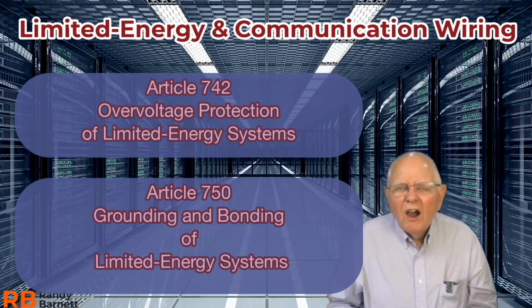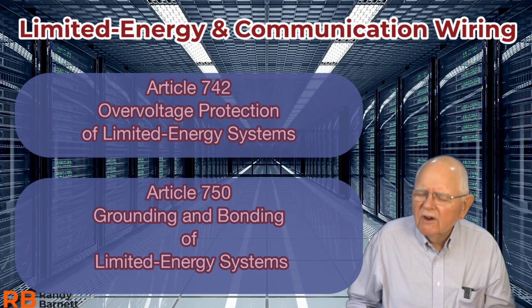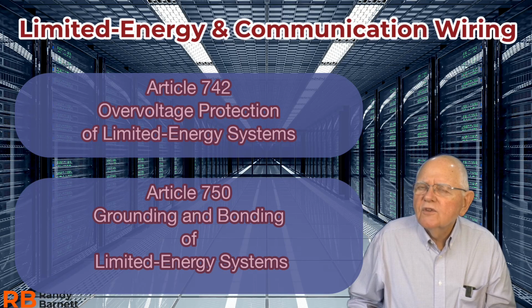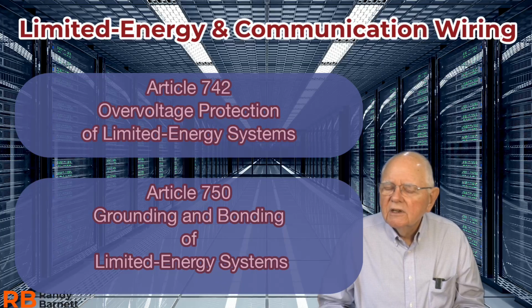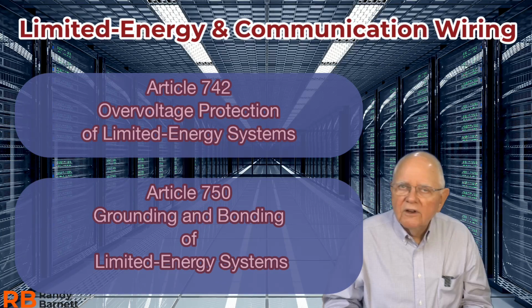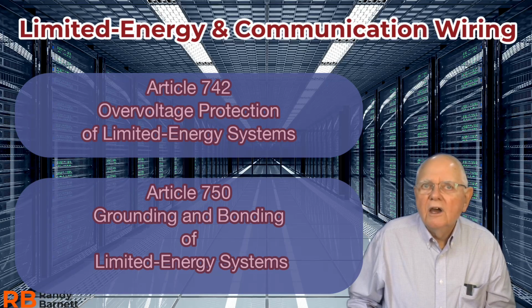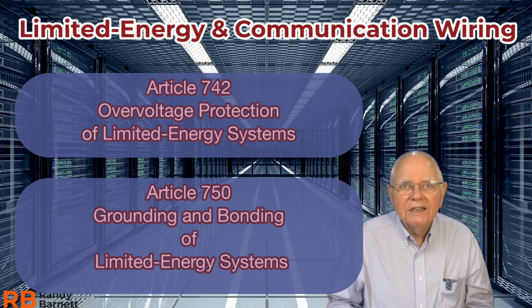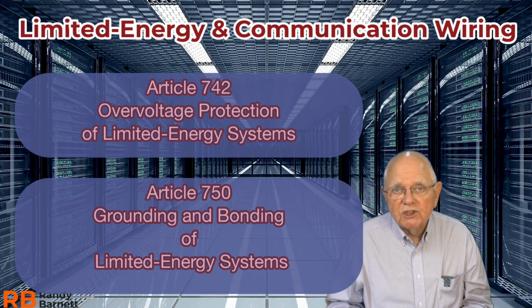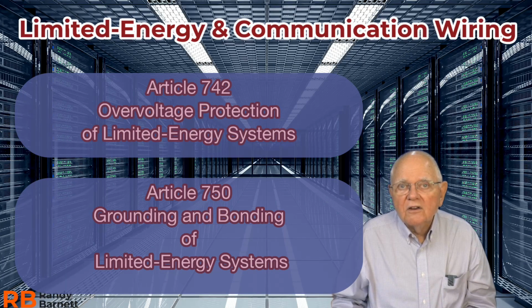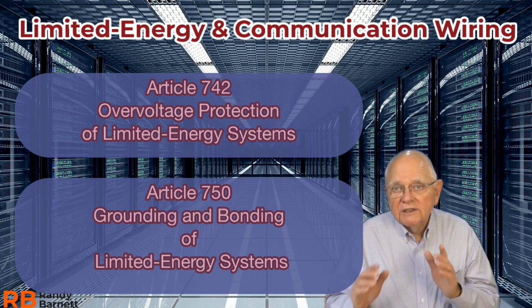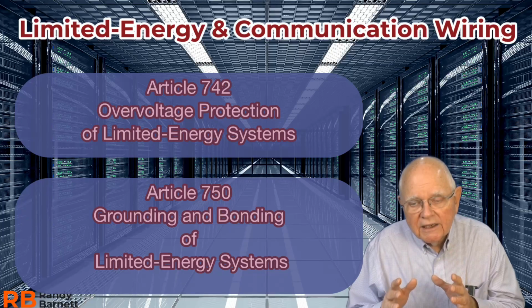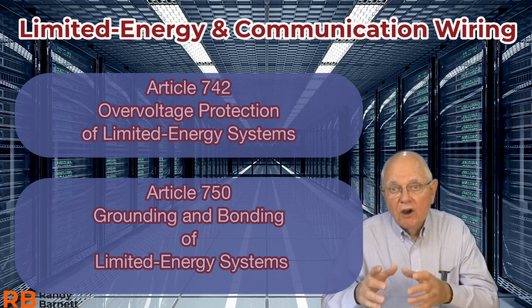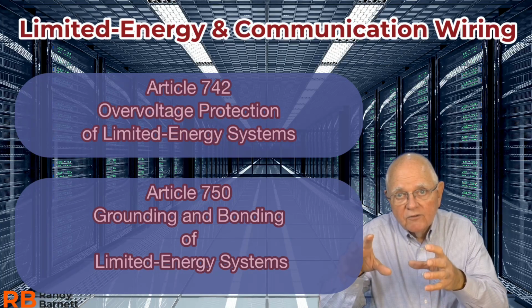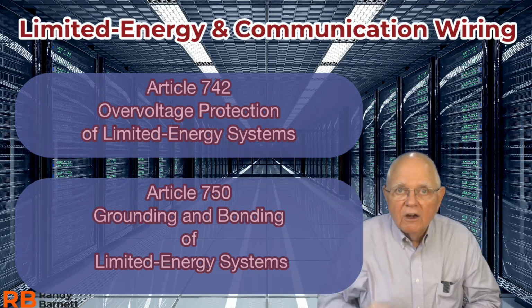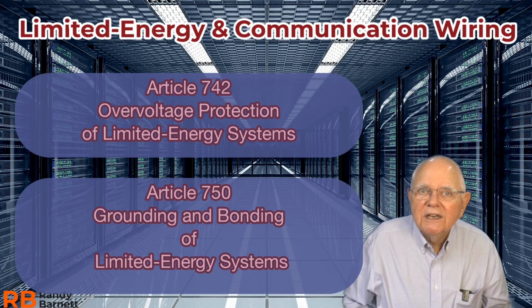Now, Article 750, we always thought Article 250 is grounding and bonding. No, they took all of this information for grounding and bonding of limited energy systems and communication systems, and they grouped it all together into Article 750. So once again, a new article, grounding and bonding of limited energy systems. It consolidates all of that information from chapters 7 and 8 into Article 750. It also took the grounding and bonding information that was in our fire alarm systems in Article 760, and moved it over to Article 750.